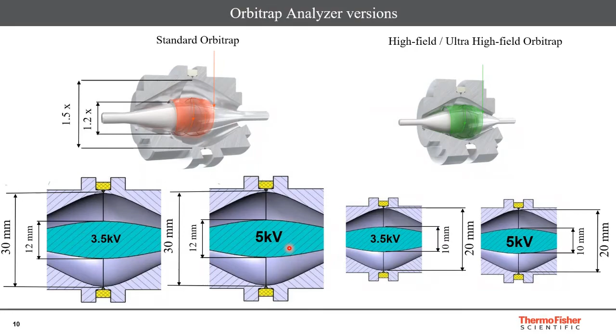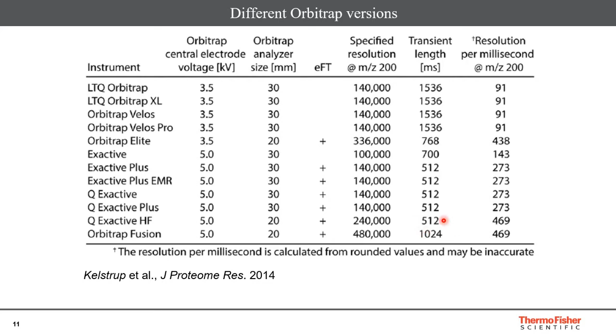All right. This particular slide tabulates the different Orbitrap analyzers. From top to bottom, it goes from standard Orbitrap to ultra high field Orbitrap. I mean 3.5 kilovolt in combination with D30, diameter 30, to 5 kilovolt, diameter 20, right? So how does this matter? What does it translate into? In the standard Orbitraps, you can attain 140,000 resolution at 1500 milliseconds. Whereas in the high field or ultra high field Orbitrap, you can almost attain double the resolution, 240,000, in almost one third the time. So here you can get it within 500 milliseconds. So that is the logic, right?